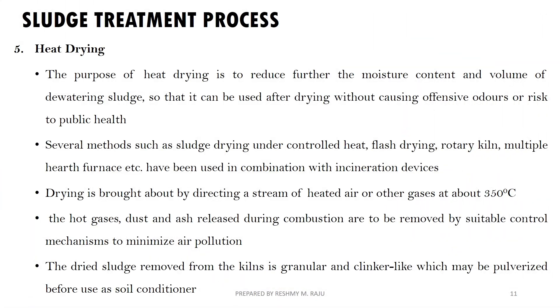We will use heat drying. We use a method of moisture content reduction to achieve volume reduction. We can use water-drying and heat drying with controlled heat methods, such as flash drying, rotary dryers, and multiple hearth furnaces. Heat drying is performed at about 350 degrees.